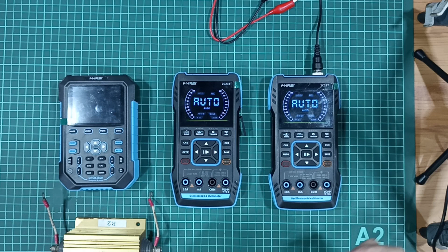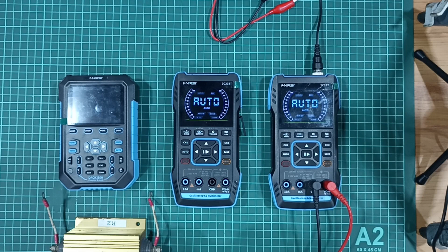And the reason for that is simple. This thing starts in auto in resistance mode. So if you've got an AC supply, the AC supply will pick up, the machine will detect it and switch to voltage. However, with the DC supply, it goes from 0 volts to full volts in no time at all. And that's what killed this one.